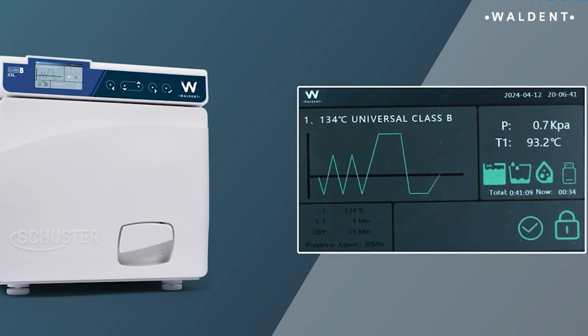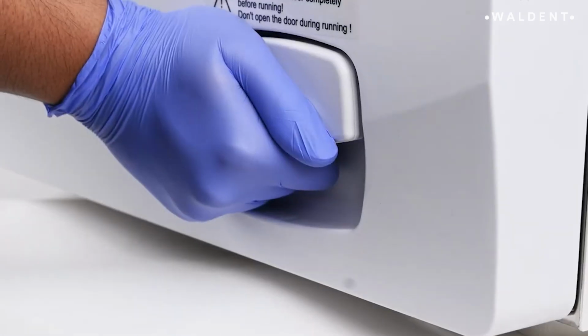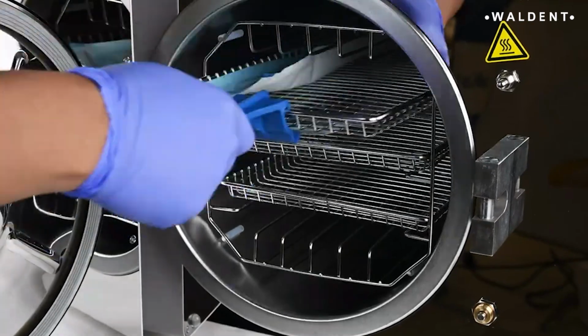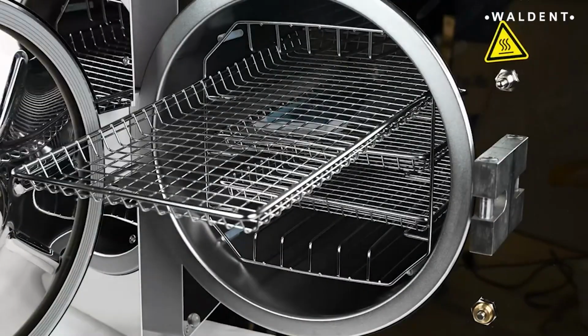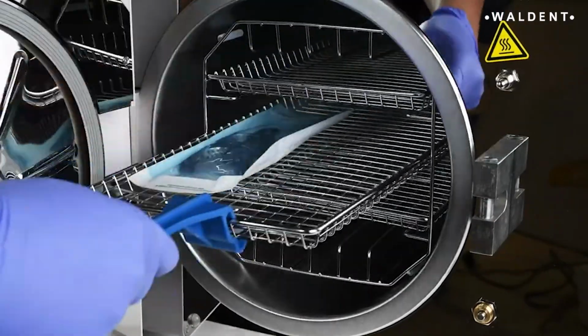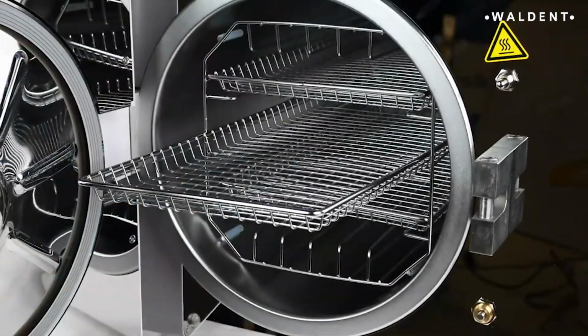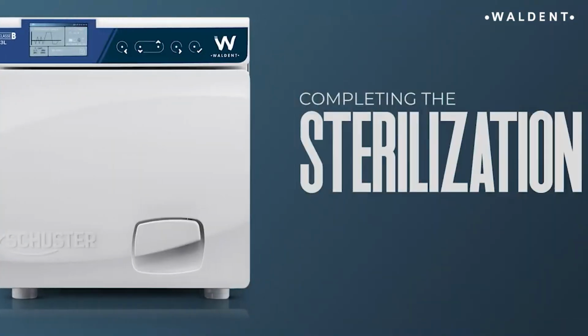At the end, display will show open the door with an alarming sound. Do not open the door till the pressure is less than 10 kPa. If the pressure level is correct, then open the door and unload the instruments from the chamber. After completing the sterilization cycle, it is important to verify the efficacy of the process.